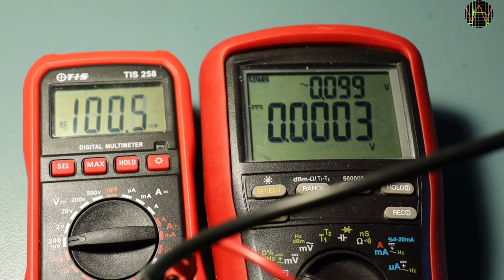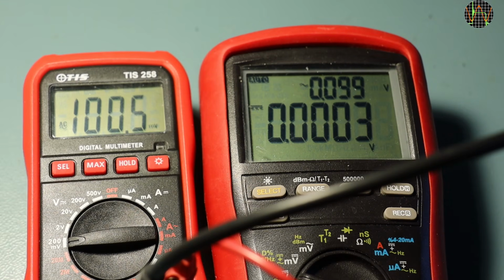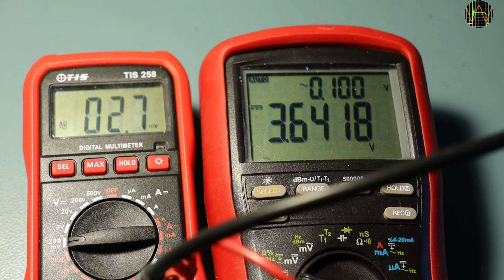The TIS-258 has problems if both AC and DC are present at the same time. Here's an example. The meter on the right shows AC on top and DC below. As I increase the DC offset, the AC readings on the TIS reduce to the point of close to 0. There's no warning or any other indication. You need to be careful with this meter and mixed AC and DC, and that applies to both voltage and current measurements. Always use the highest range first to check if such a condition is present.